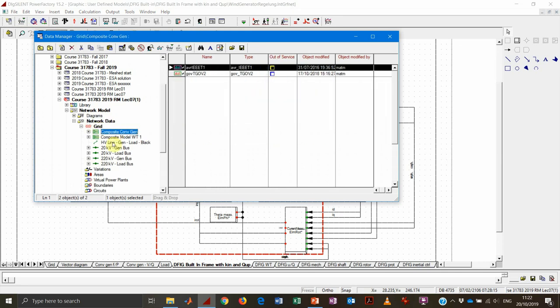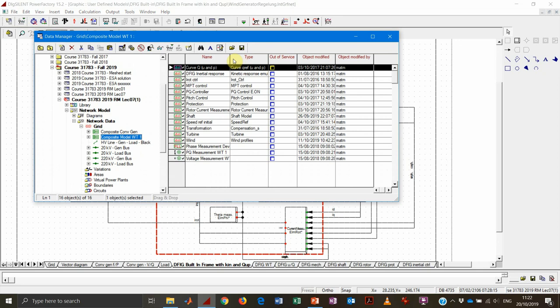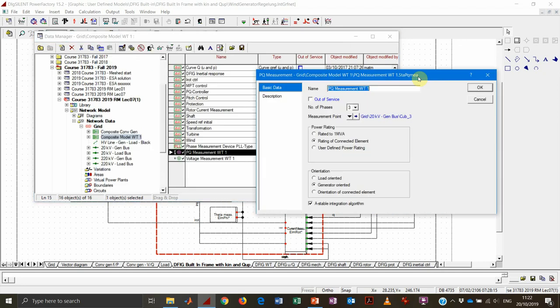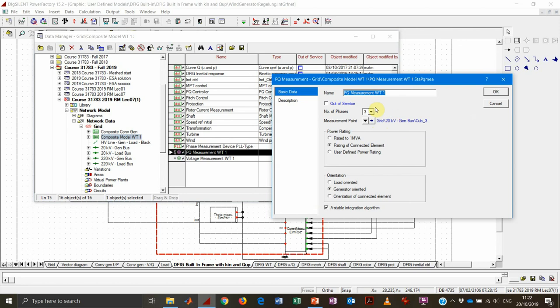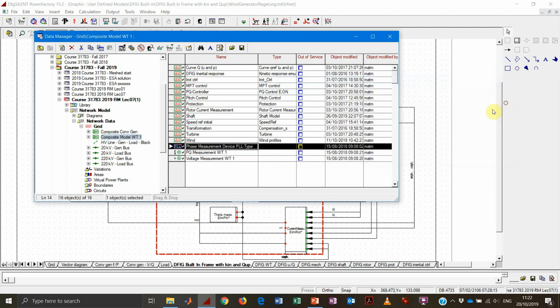Everything is set in the composite model. You can see that there are several common models — many more than for the conventional machine. Most are common models and there are also a couple of measurement blocks: active and reactive power measurement at the machine connection point, voltage measurement at the connection point, and a PLL (phase measurement device) also at the connection point. All these are necessary for both converters to perform their control and adjust power production according to grid voltage, frequency, and so on.